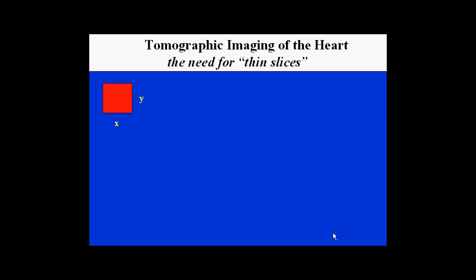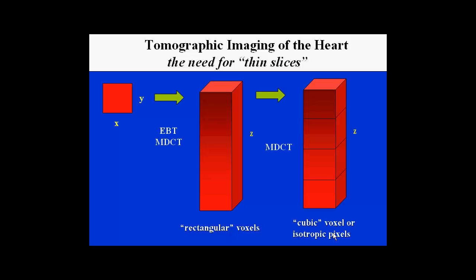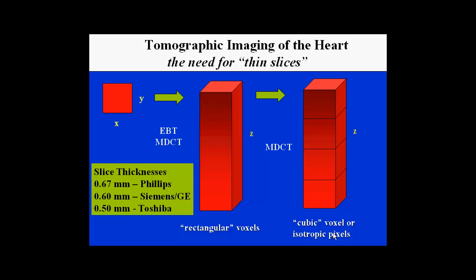In the XY plane, we have excellent resolution using standard CT, well below one millimeter. However, with older multidetector and electron beam CT, there is a Z thickness that results in rectangular voxels. The important innovation with 64-slice CT is that we can acquire images in XY and Z planes that are isotropic — meaning, as with isobars in meteorology, any direction in the XY, Z, or off-axis plane has exactly the same dimension. Slice thicknesses vary by manufacturer: 0.67 millimeters for the 64-slice Philips scanner, down to 0.5 millimeters for the Toshiba 64-slice scanner.